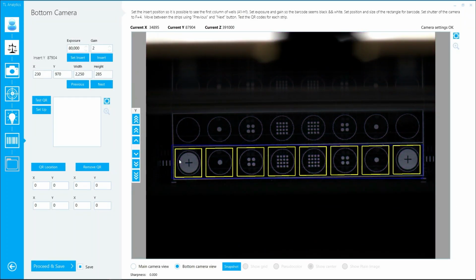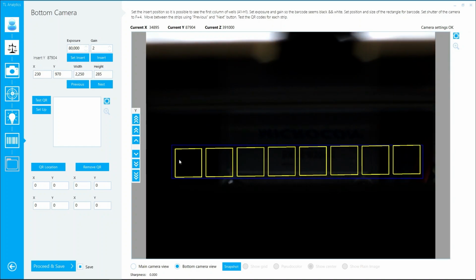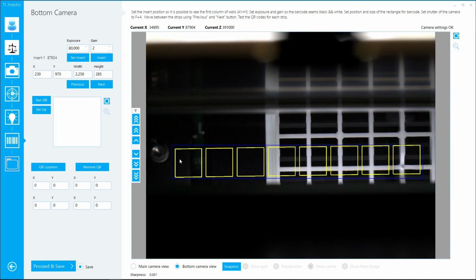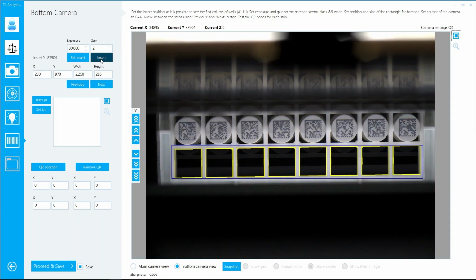So the next step is bottom camera, the barcode reading. First thing you need to do is insert the real MBA microplate with the barcodes at the bottom of each well. Take out the first strip and leave this first position empty so the camera can focus and set the position of the grid. So after you insert the plate, press insert to set it to an insert position focused on the first strip. So when you have the plate in position, click on QR location.